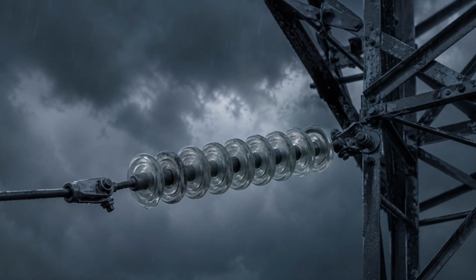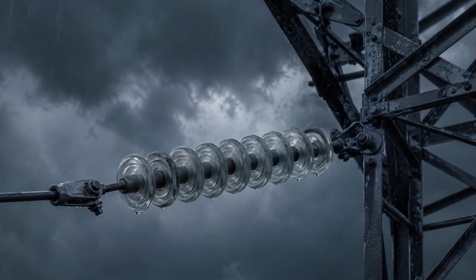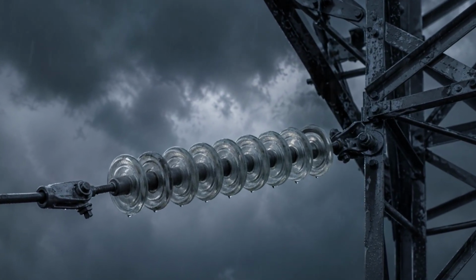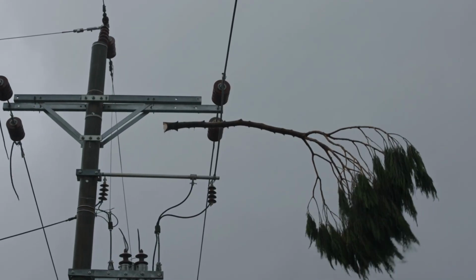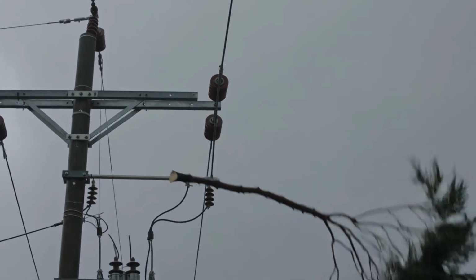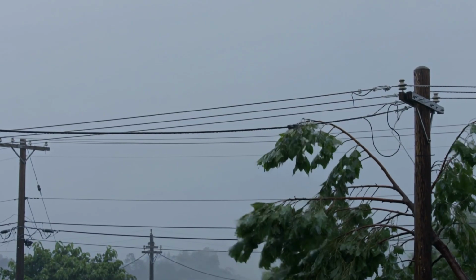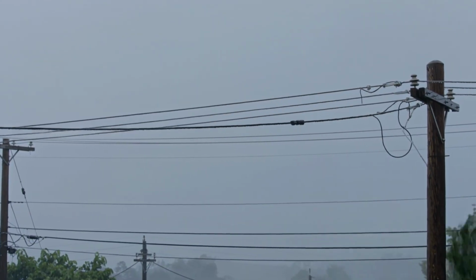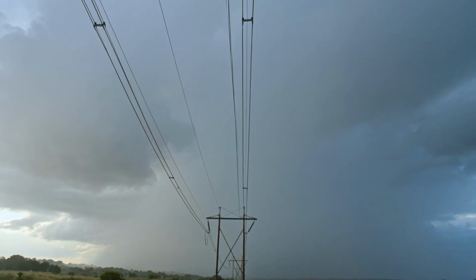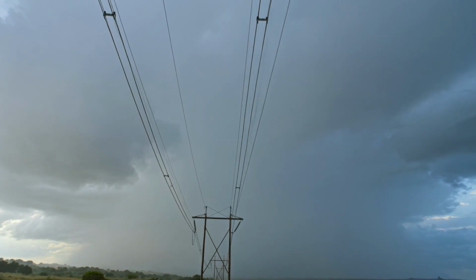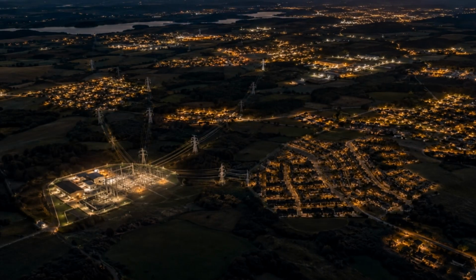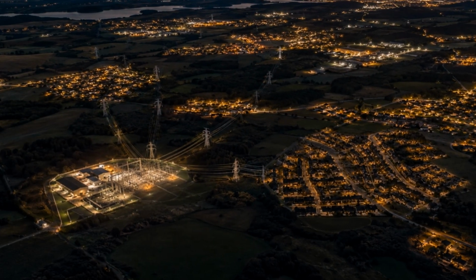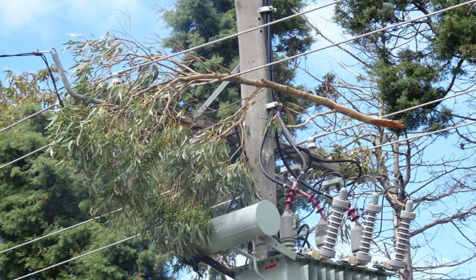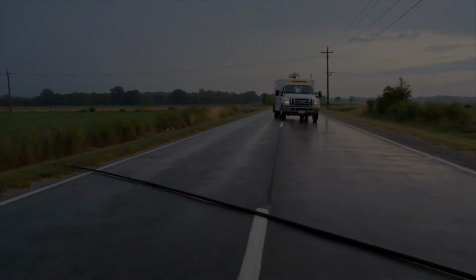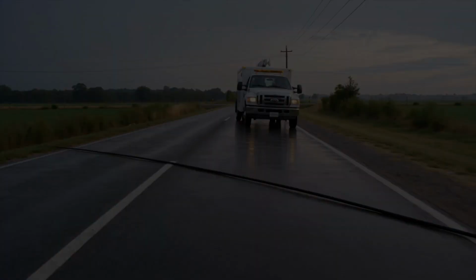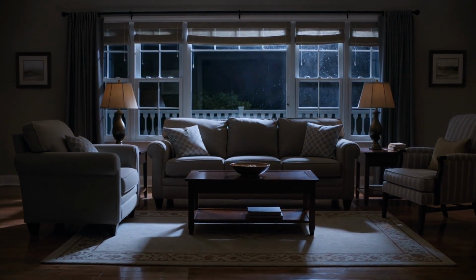Many overhead line problems disappear almost immediately. The lightning arc dies out, a branch touches the wire, then falls away. Or strong wind briefly pushes something too close. So after a short pause, the grid tries the line again. This is called automatic reclosing. If the problem has gone, the power stays on. If it is still there, the line switches off again and waits for a crew. That is the blink you see during a storm.